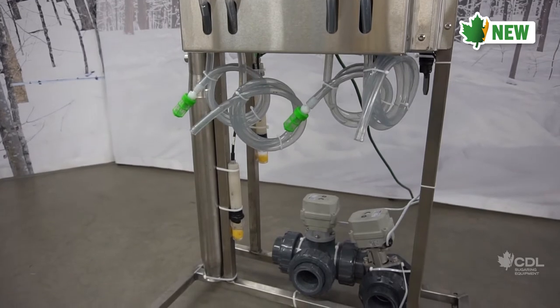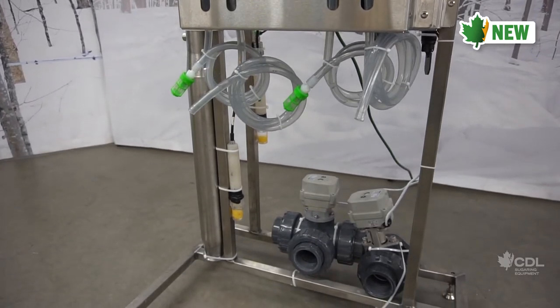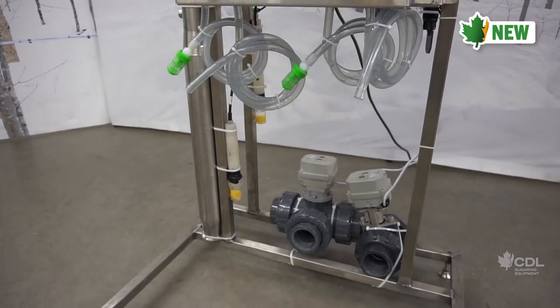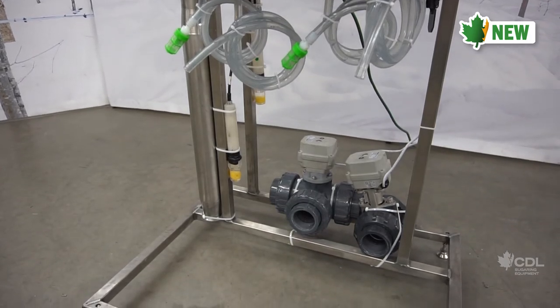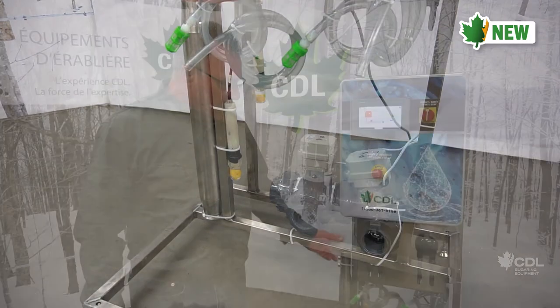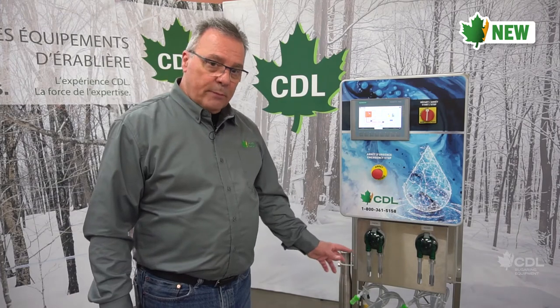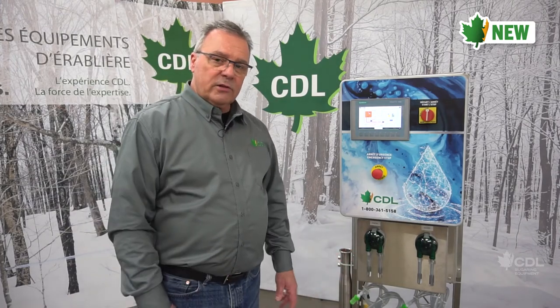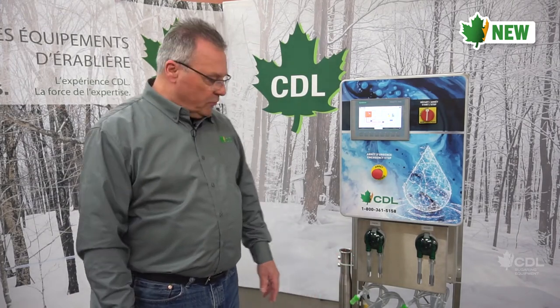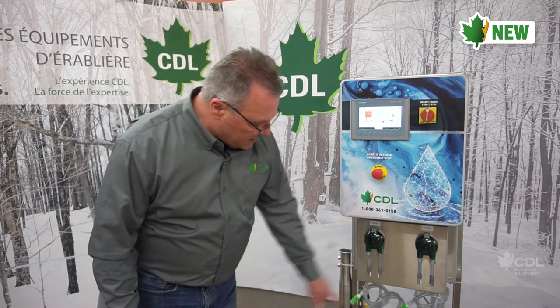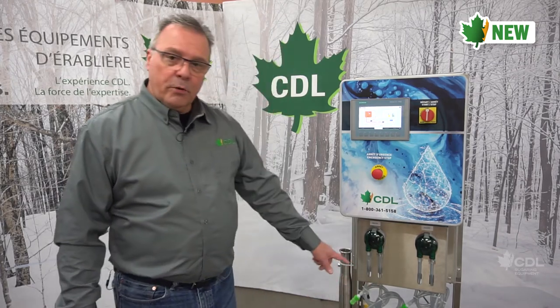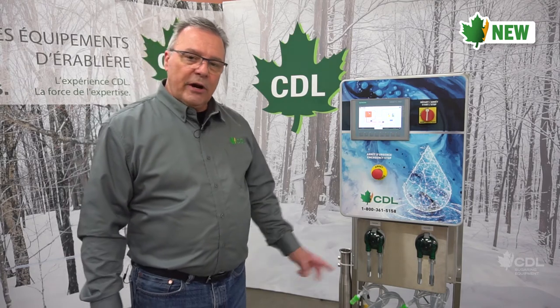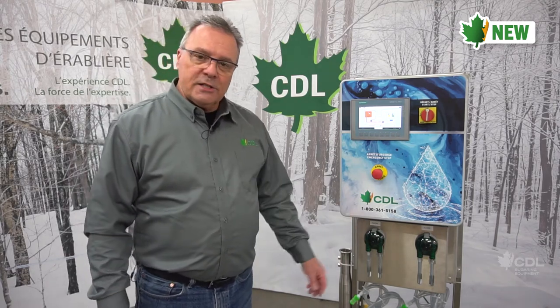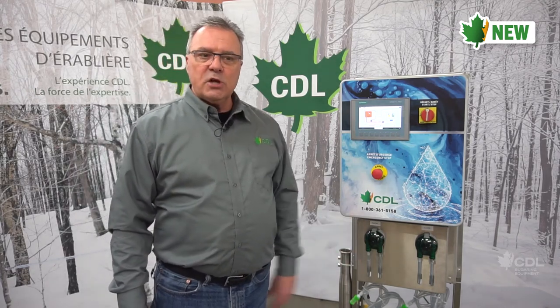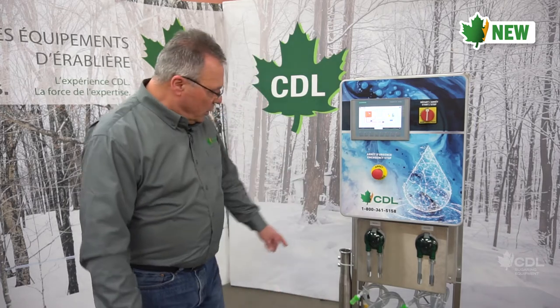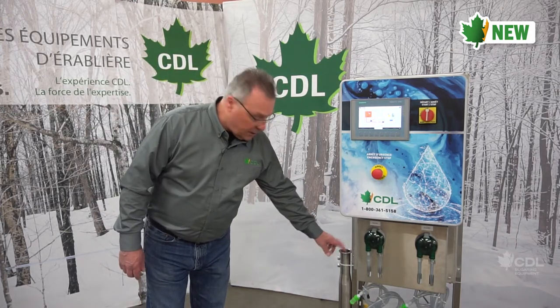So the system is equipped with two valves. So you have a three-way valve, which normally is directed towards the neutralization tank. But once the pH reaches 6.5 to 9.5, then it can be directed directly to the dispersion field. The other valve is a single-way valve, and the purpose of that valve is to drain the neutralization tank once the neutralization is completed.